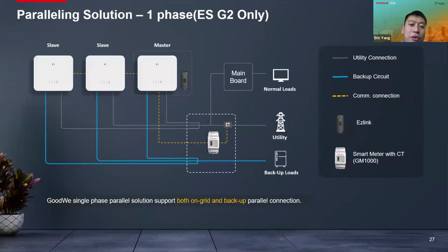And this is a parallel solution for the ESG2 series. We have realized both on-grid and backup parallel connection. In this diagram, we will have one master inverter and multiple slave inverters. The master inverter will install a different communication module. We call it Ezlink. And if the inverter has the Ezlink installed and is also connected to the smart meter and the CT, we call it the master inverter. And the other slave inverters will have the communication cable to the master inverter.